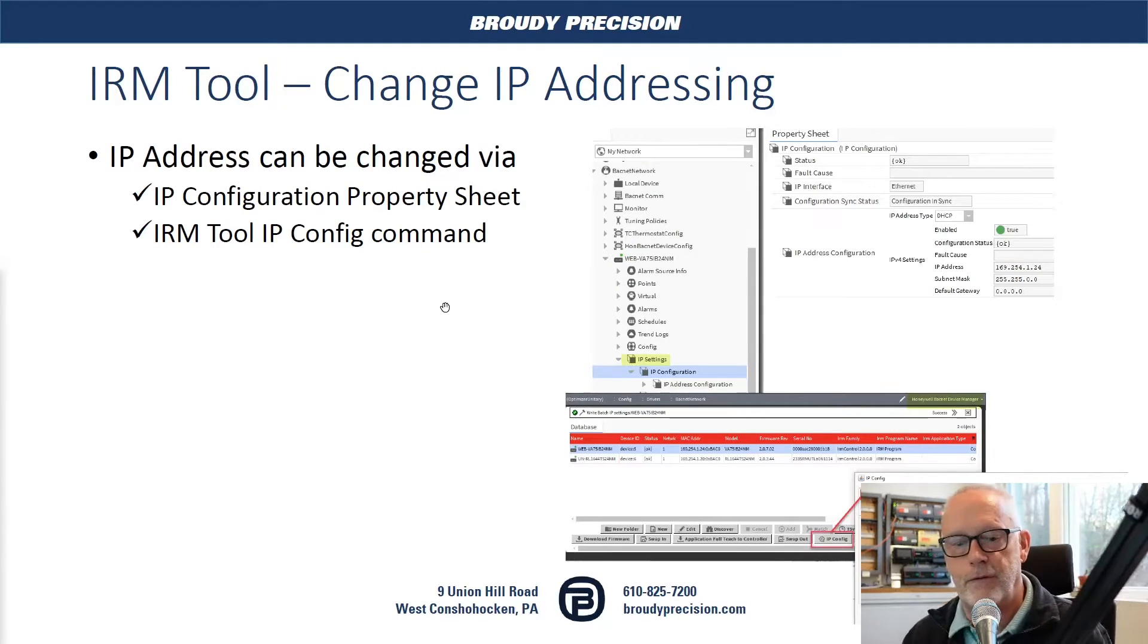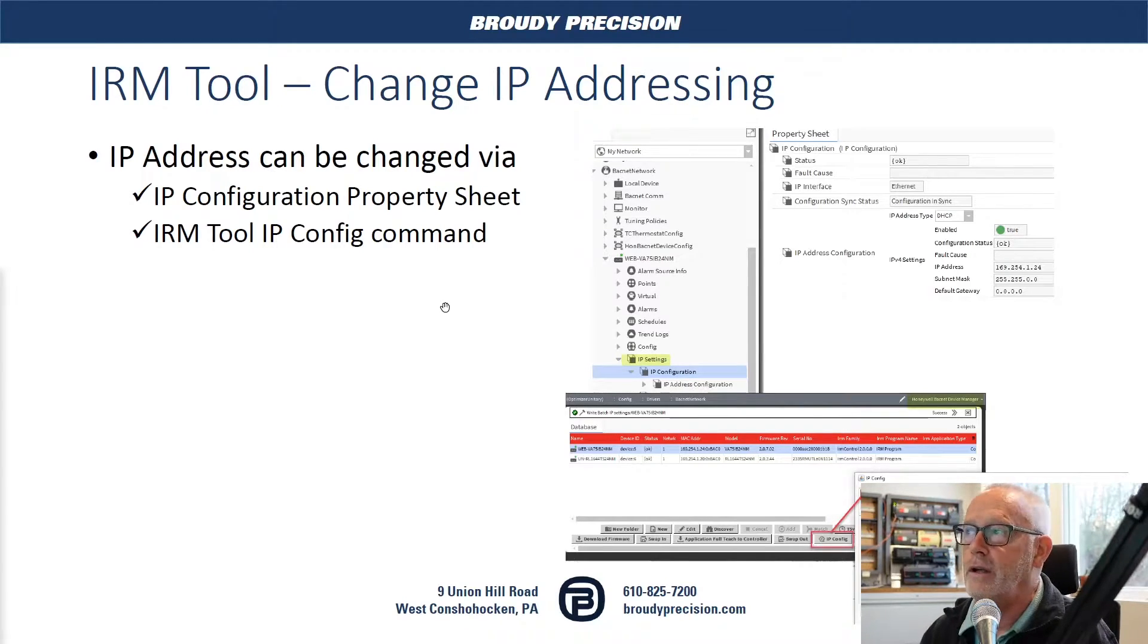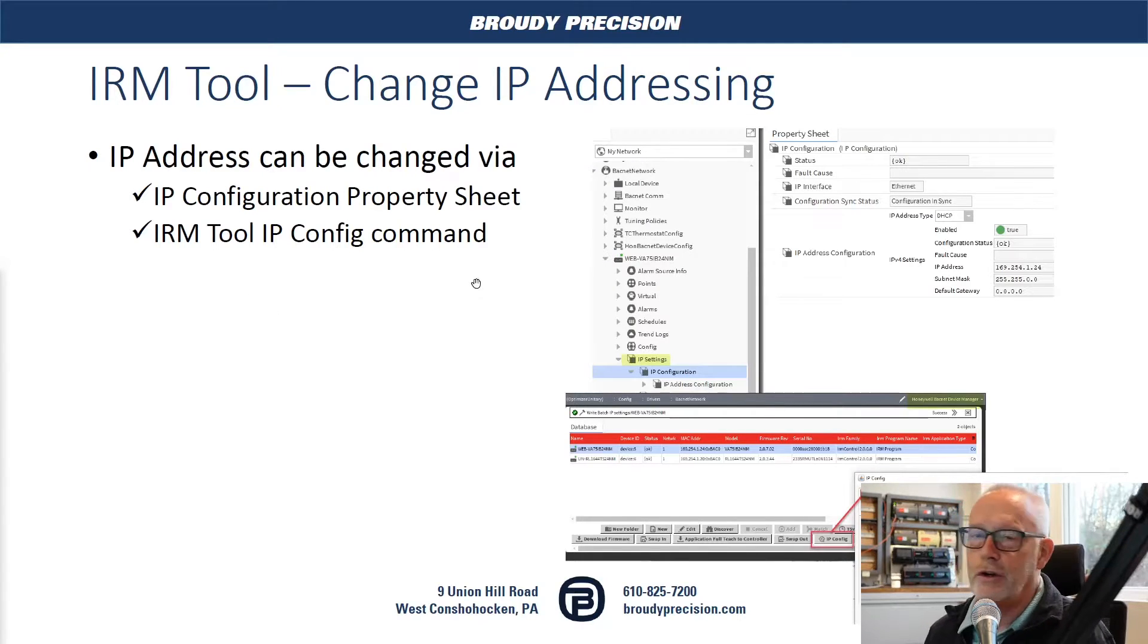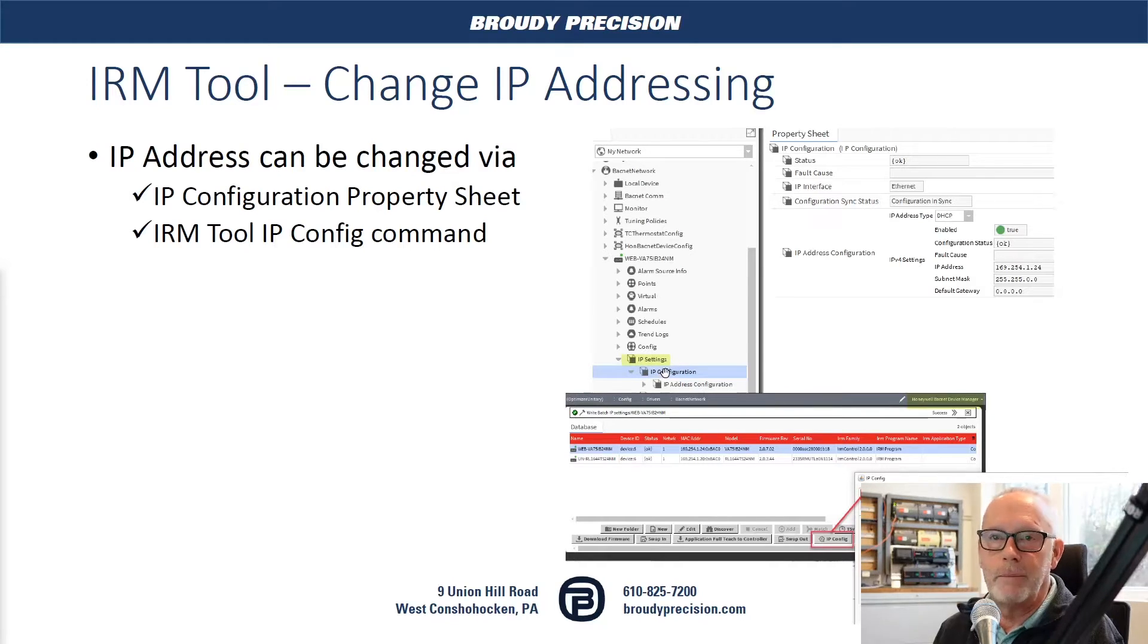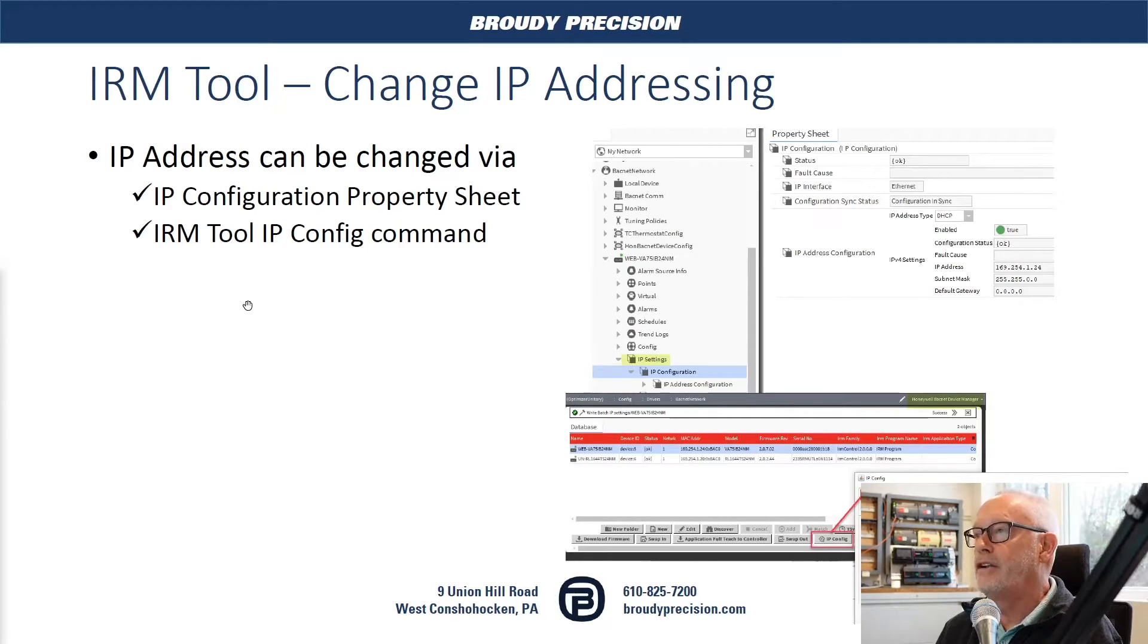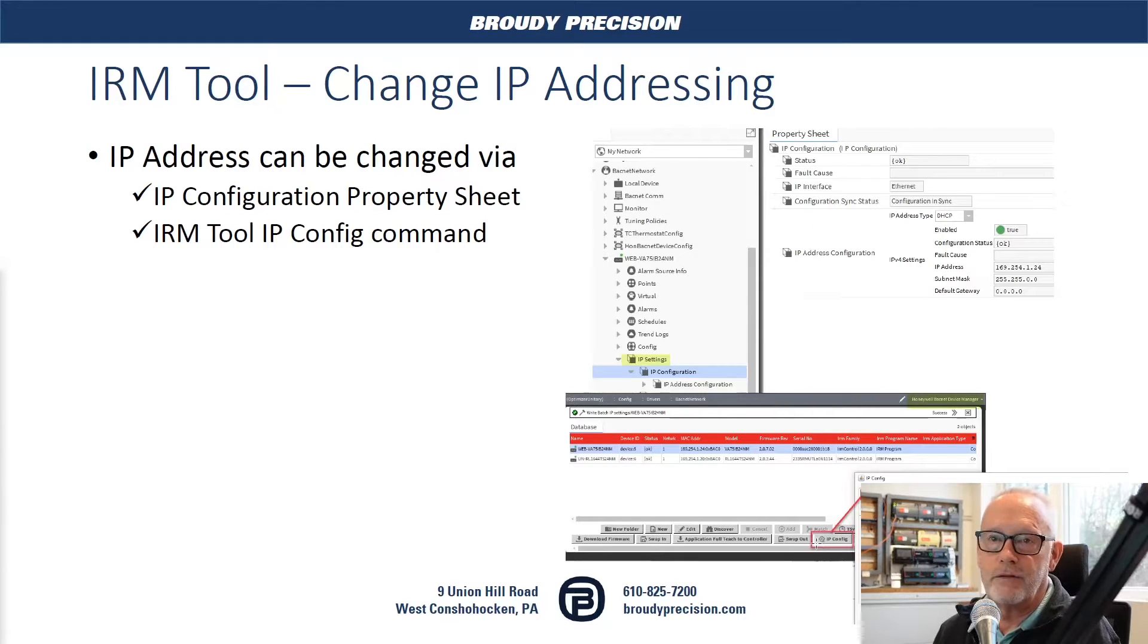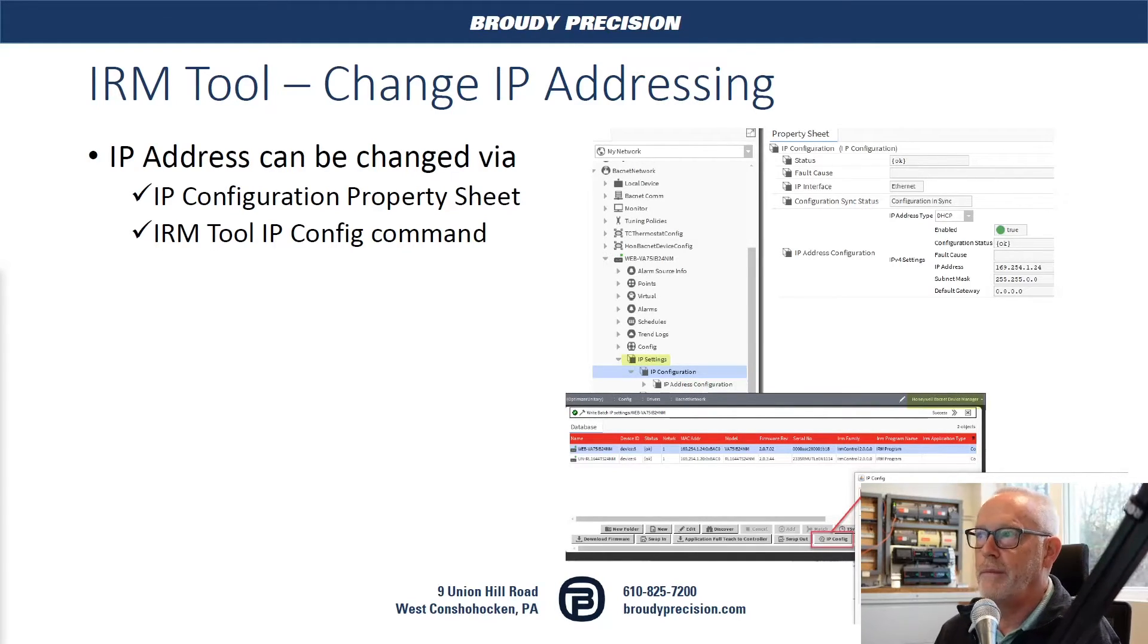Once you have that done and you go in and discover and bring the controllers into Niagara, you can go in and change the IP addressing in two different ways. You can go to your nav tree and look at your controller. There should be an IP settings slot there. You can go to IP configuration from there. Or you can go to your device manager view. And from there, you can select your controller, and then you would select IP config. And it would bring up the dialog box to change from DHCP to static or static to DHCP. And you can make your changes from there.